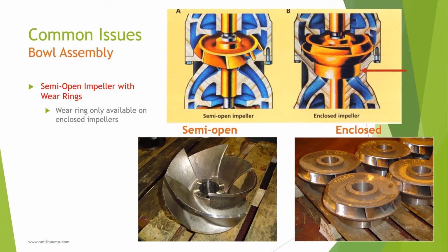Semi-open impellers seal between the vane and the bowl, so there's no place for a wear ring to be used. So here's a quick side note on the advantage of the semi-open impeller. They seal against the bowl on the vane edge, right there, with a very tight tolerance. Because of this tight tolerance, the resistance to recirculation, they're typically more efficient than enclosed impellers.